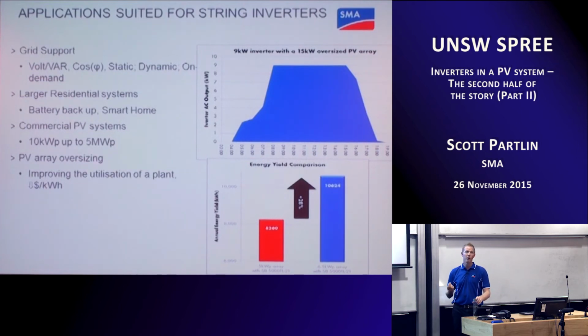PV array oversizing involves installing more DC power than the inverter's rated AC power. And why would you want to do that? Well, you can see here, I've just done a simple model in our online design tool where I've got a 15 kilowatt array with a 9 kilowatt inverter, and it's showing the output throughout the day. I just picked a typical summer day, and you can see how the production comes up very high in the morning and then is lopped off during the middle of the day because the inverter is not able to convert all of that DC into AC, and then drops off nice and sharp in the evening.